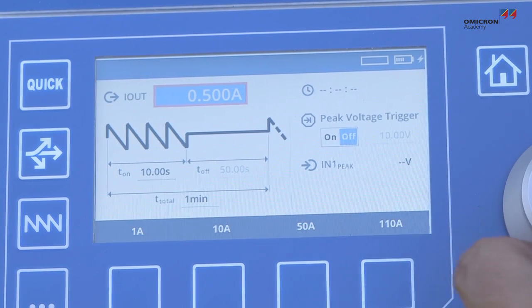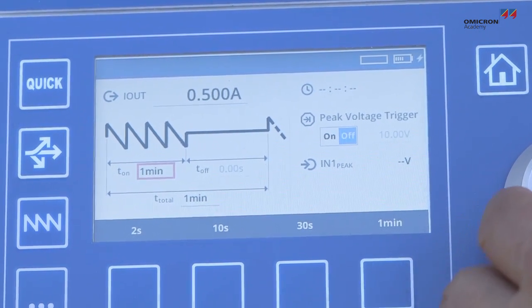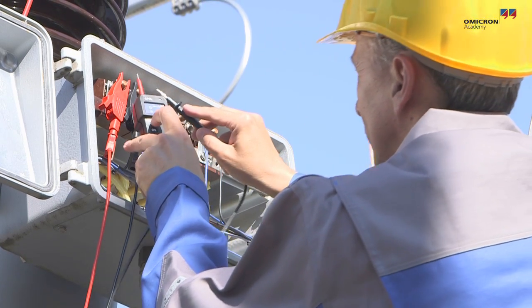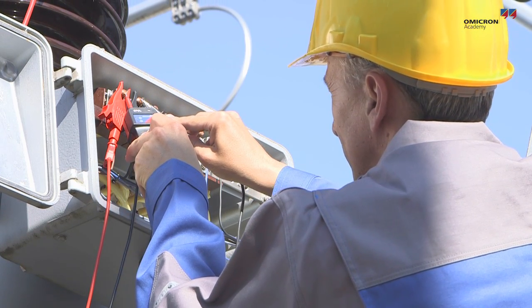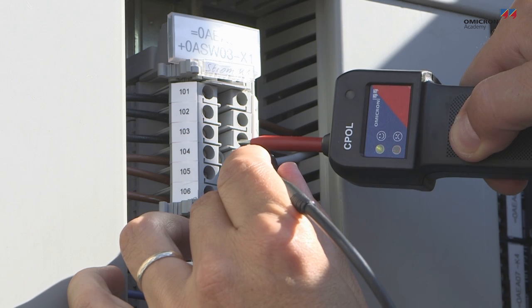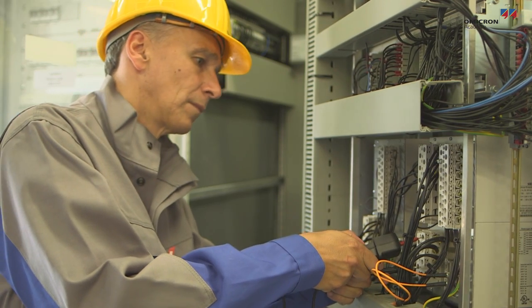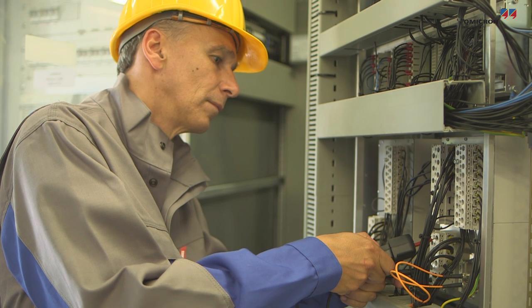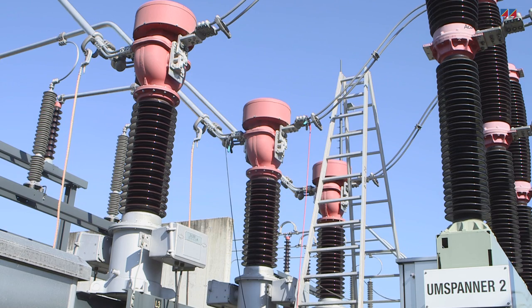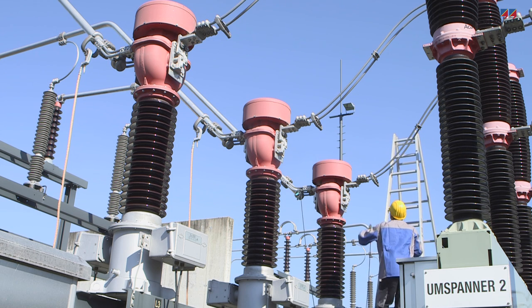When a sawtooth signal with a distinct polarity is being used for injection, a handheld device can be used to validate the polarity throughout the system — from the secondary side of the CT, along the secondary wiring, all the way to the last terminal. Since this test is done phase by phase, all of the potential wiring errors or phase swaps can be detected.